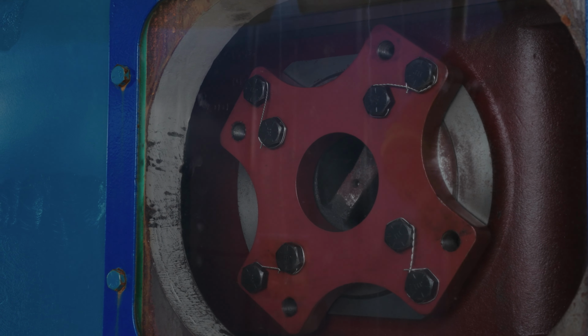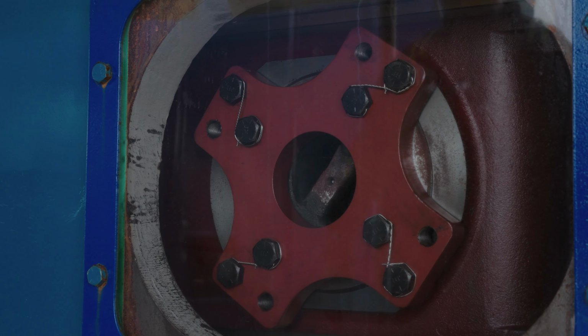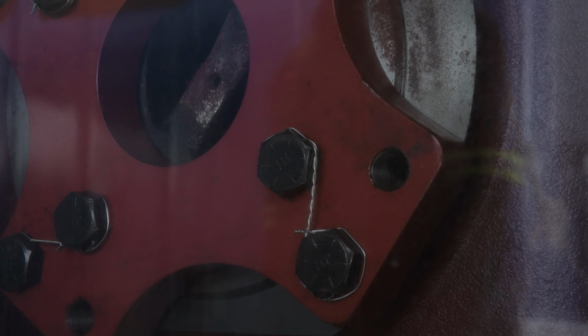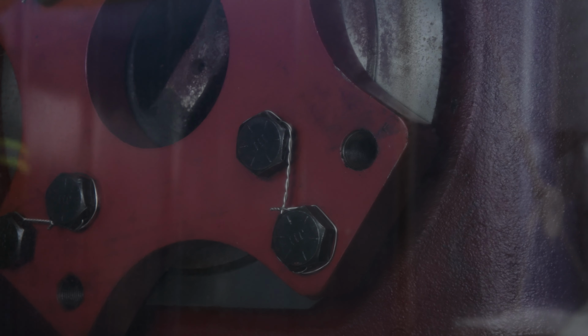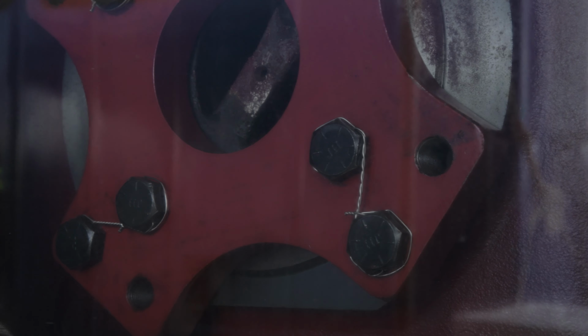Make sure the nozzles are spraying on the crosshead and slide. Check for broken tie wires on pony rod bolts and crosshead nuts. And look for unusual or heavy scarring on the slides. On the outside, make sure there are no leaking gaskets or loose bolts on the crosshead inspection frame.